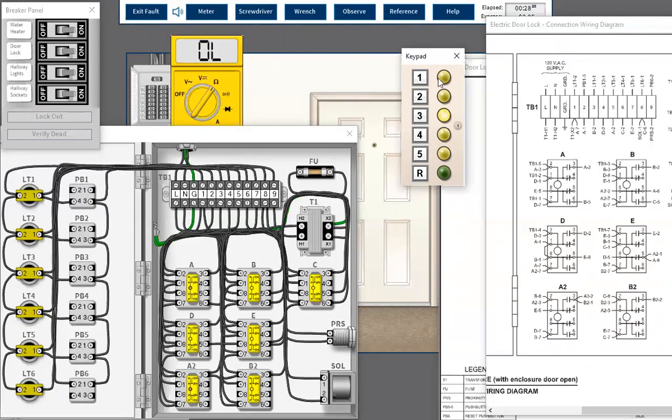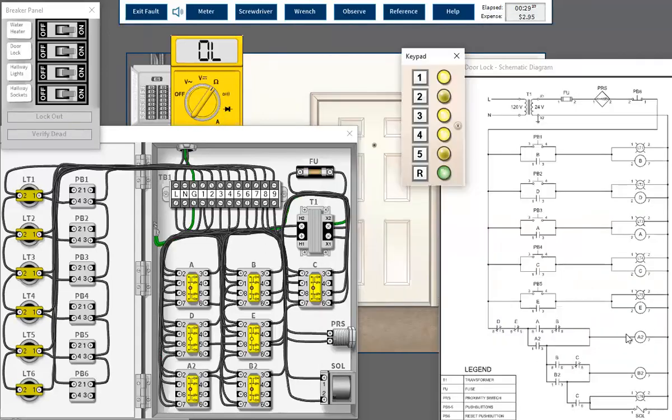So we go 3, 1, and guess what? A2 stayed on and B2 stayed on, and 4. It took me a second there because I was following through and voltages looked fine, but really I did not pay attention to that relay coil. It went off when you hit 1. So the seal-in contact on that relay is what got us. No, I'm sorry, the wire from this point to there, that wire to seal in, was bad. It was open, so you can't maintain power through this A2 to the coil. But we're good.